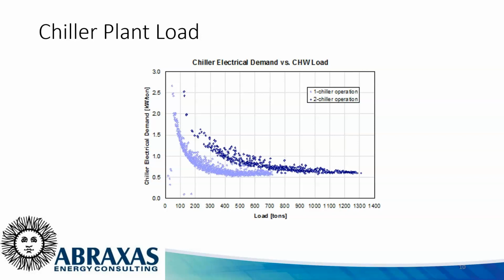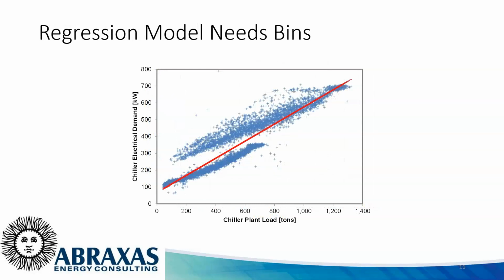It just makes it a more complicated curve like this. If you just plot the data as kW versus tons, you essentially get a straight line. So here's the same data shown as just kW versus tons, with the same two clouds of data. The point here is the title says a regression model may need bins - you need to categorize the data. You don't want to draw a single line through both clouds of data. It might be okay in some cases depending on your purpose, but obviously you get a better model if you segment it for one chiller versus two chiller operation in this case.